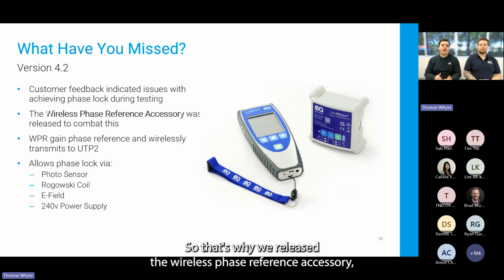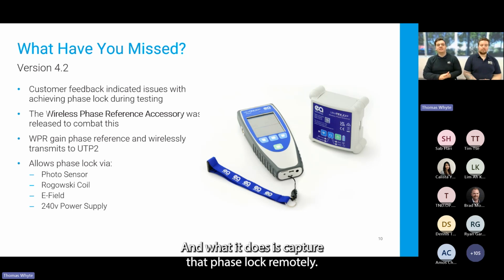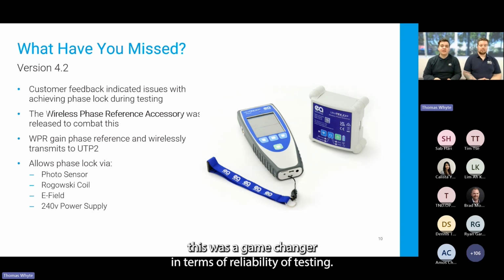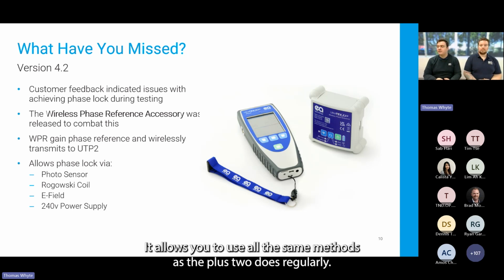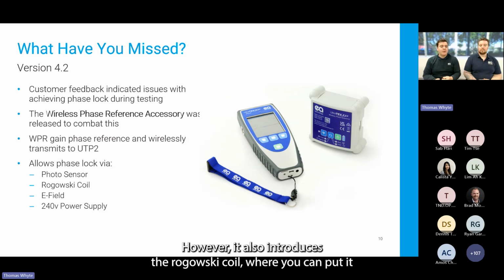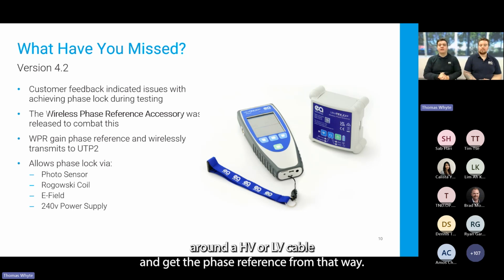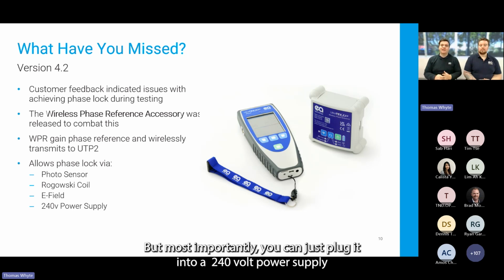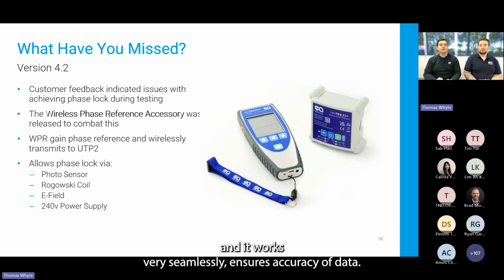That's why we released the wireless phase reference accessory, that small blue box on the right. It captures the phase lock remotely and sends it via Wi-Fi to the +2. For me, as someone doing this testing in the field, it was a game changer for reliability. It lets you use all the same methods as the +2 normally uses, but also introduces a Rogowski coil you can put around an HV or LV cable to get the phase reference that way. Most importantly, you can just plug it into a 240-volt power supply and it works seamlessly, ensuring data accuracy. This was a big one.